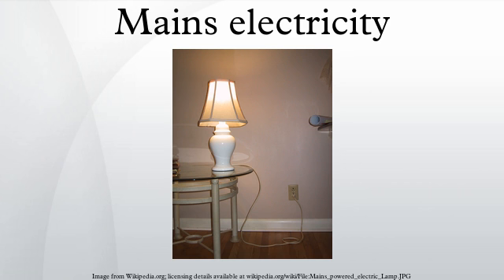The ideal voltage difference between earth and neutral is 0 V, as neutral is connected to earth at the main power panel to prevent electrocution. The practical voltage difference between earth and neutral is 0.1 V to 1.5 V, as per the impedance difference between the earth wire and neutral wire. A ground wire has a much lower electrical resistance than a neutral wire, which results in a difference of electrical potential between them, earth and neutral.